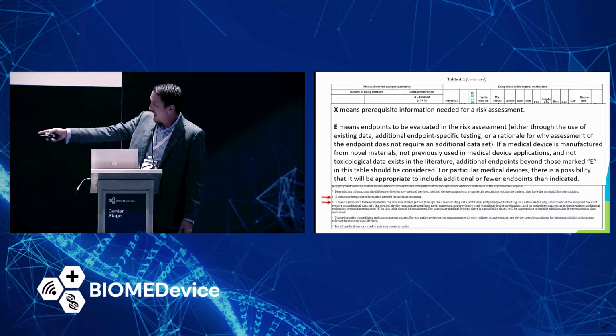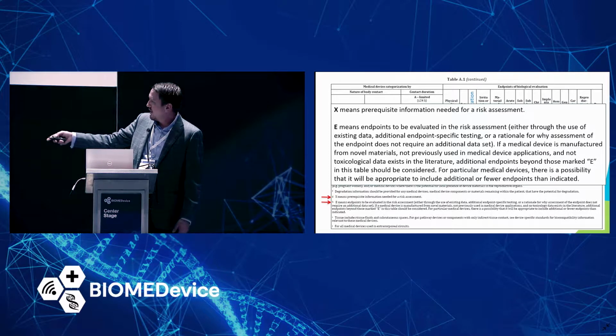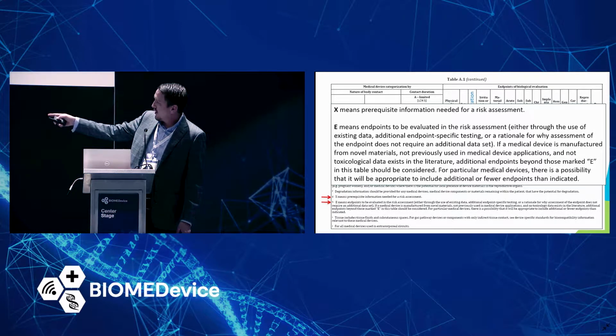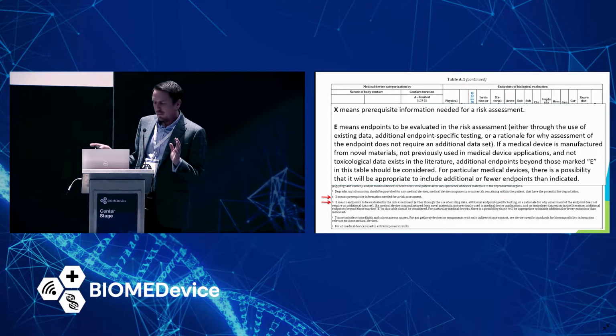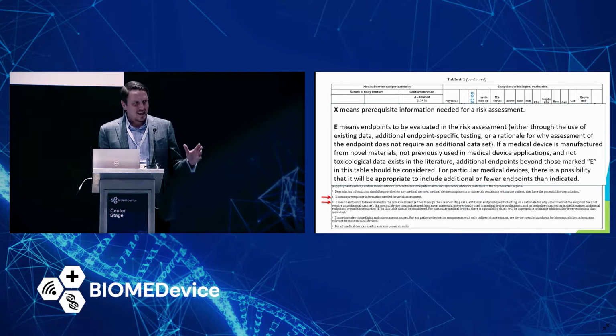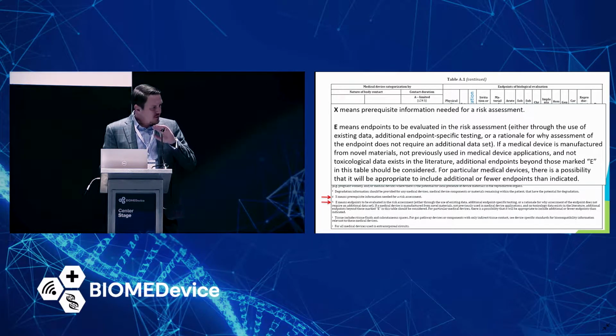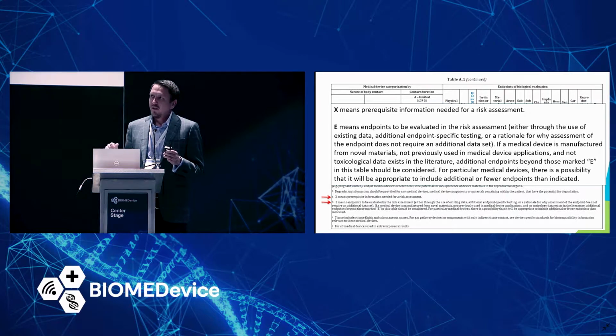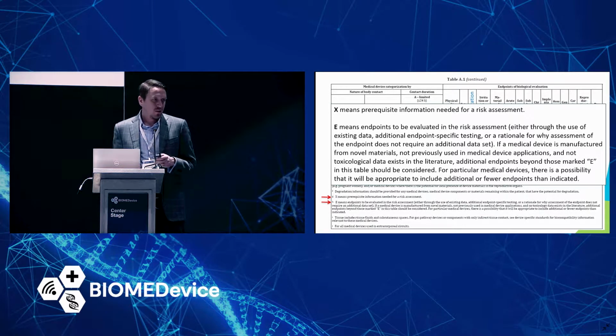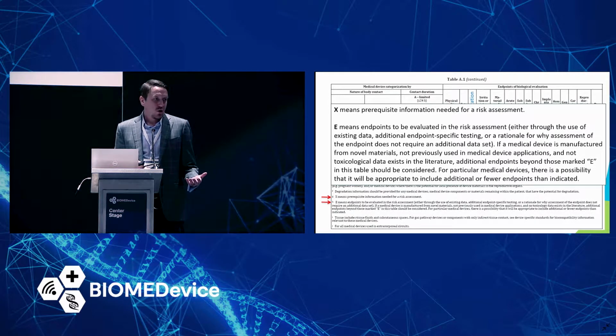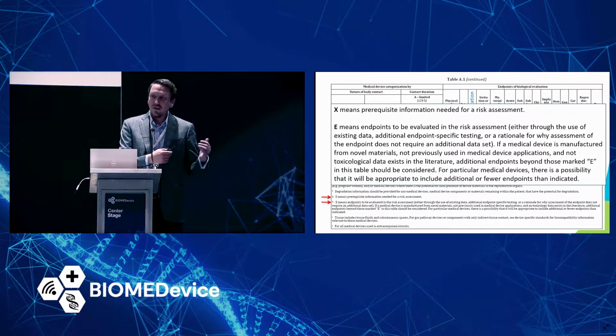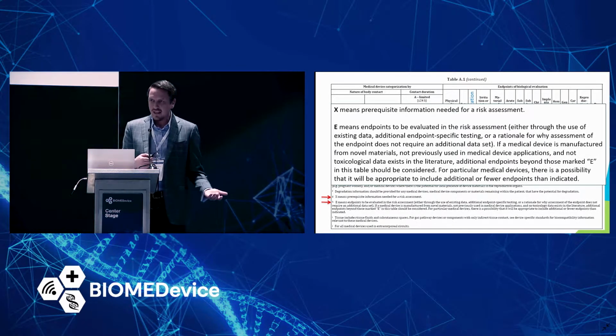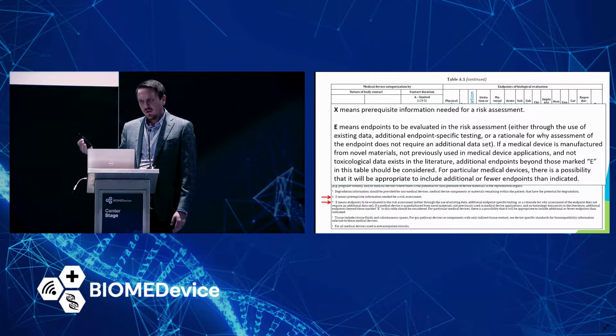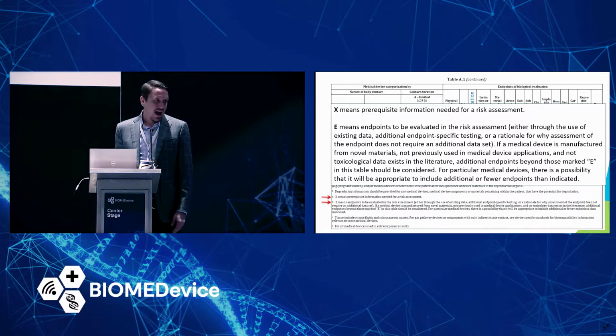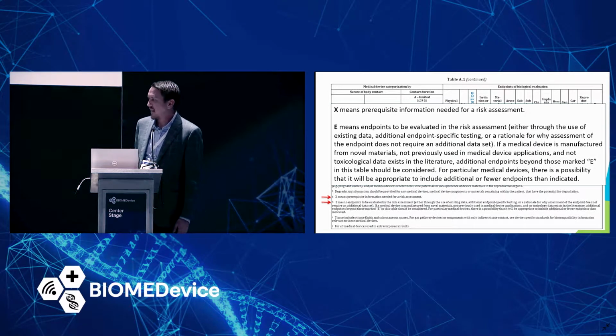These notes at the end explaining the X and the E are really important. X means a prerequisite information needed for risk assessment. I'm just gonna pause there for a second to highlight this theme. So the idea is to use a risk-based approach and not do unnecessary testing. We ought to understand enough about our materials to know if that testing is required. So if you're going to test, you need to know that you need to test first. So it's a prerequisite to doing any testing before you use animal life. You should say, okay, this is the knowledge gap that we have that justifies the use of this animal life.